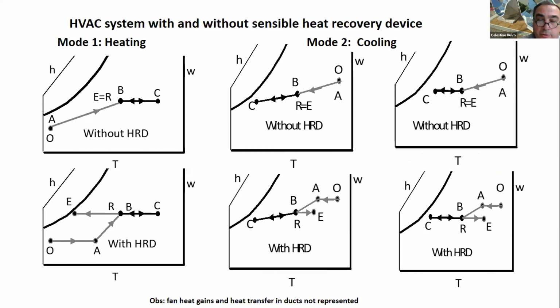In this slide, you can see the expected evolutions of the different airflows at the different components of the system for both heating and cooling modes. In the cooling mode, it is represented the case where the cooling coil is dehumidifying the air, and also the case where the cooling coil is operating in dry mode as a sensible cooler.